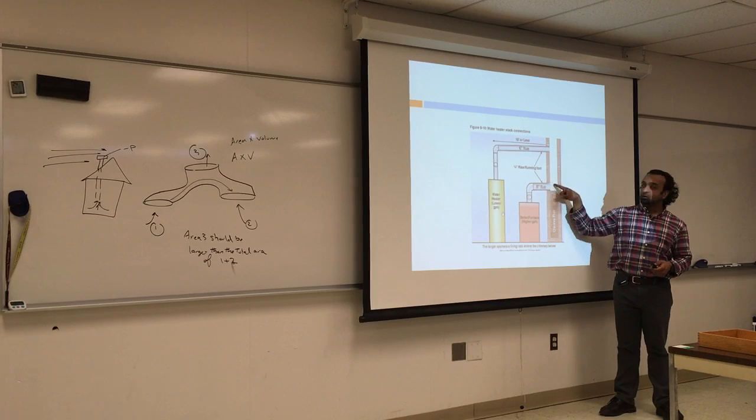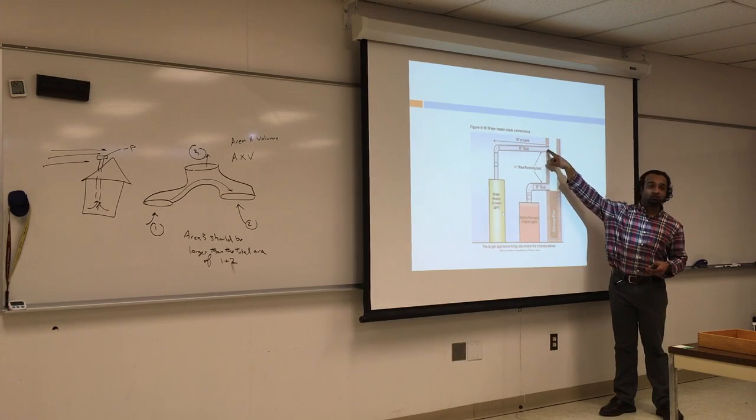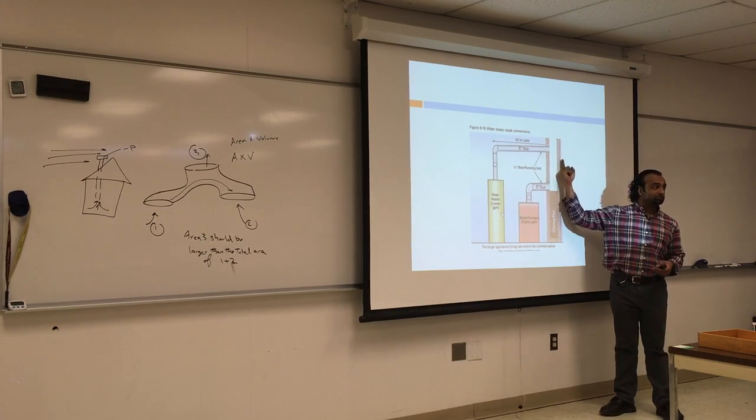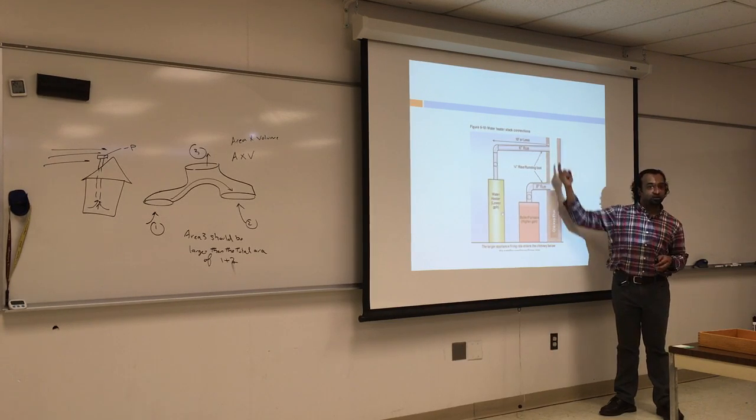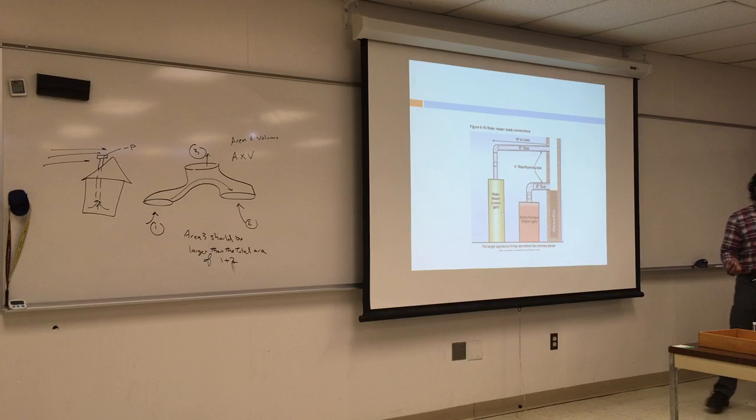Why is that? Because this is going to blow up more hot air. So if this is blowing more hot air at the top, the little one will be blocked. It will not have enough venting to go through. And I've seen this at least 2 or 3 times in installations. Because it's denser than the air above it, it basically hits a wall and stops. There will be a lot of flow in here, so it's not going to vent very well. So these are really nice, small, trivial pieces of information, but they make a big difference when it comes to troubleshooting. And again, just because something was running for a while and stopped running, you should not skip going to check the installation.